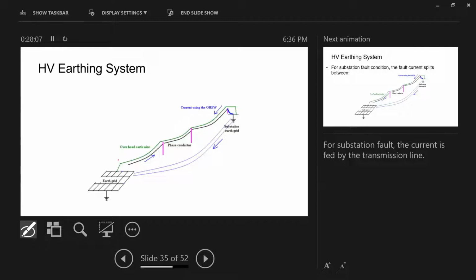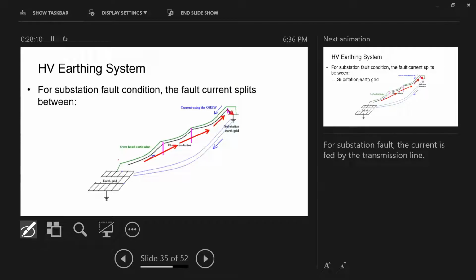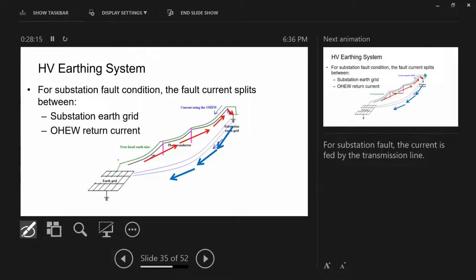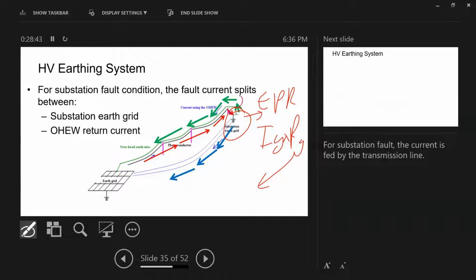Look what will happen under fault current. When I have a fault current, our substation earth grid will force the current to go back through the ground. That's the current that goes into the ground, and I will have an EPR, earth potential rise, which is equal to IG multiplied by RG. This RG depends on your earth grid system, that's the steel that is put into the ground. Now, part of it will go back through the overhead earth wire, part of it will remain in the overhead earth wire.